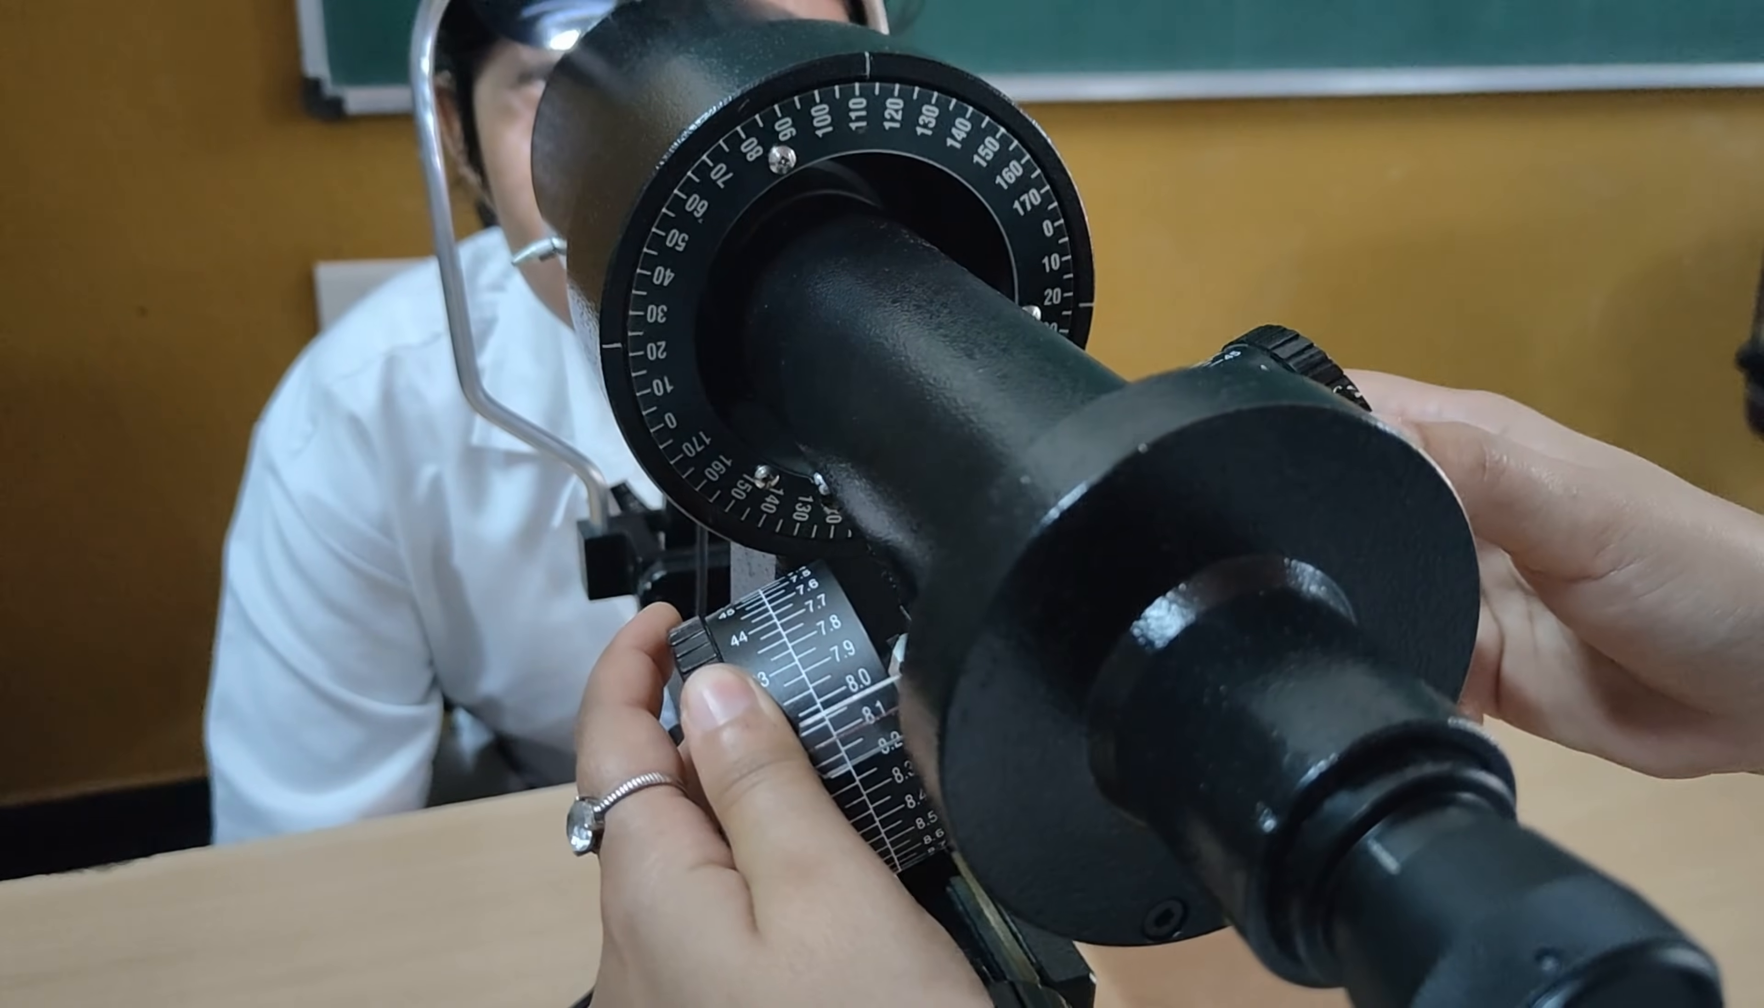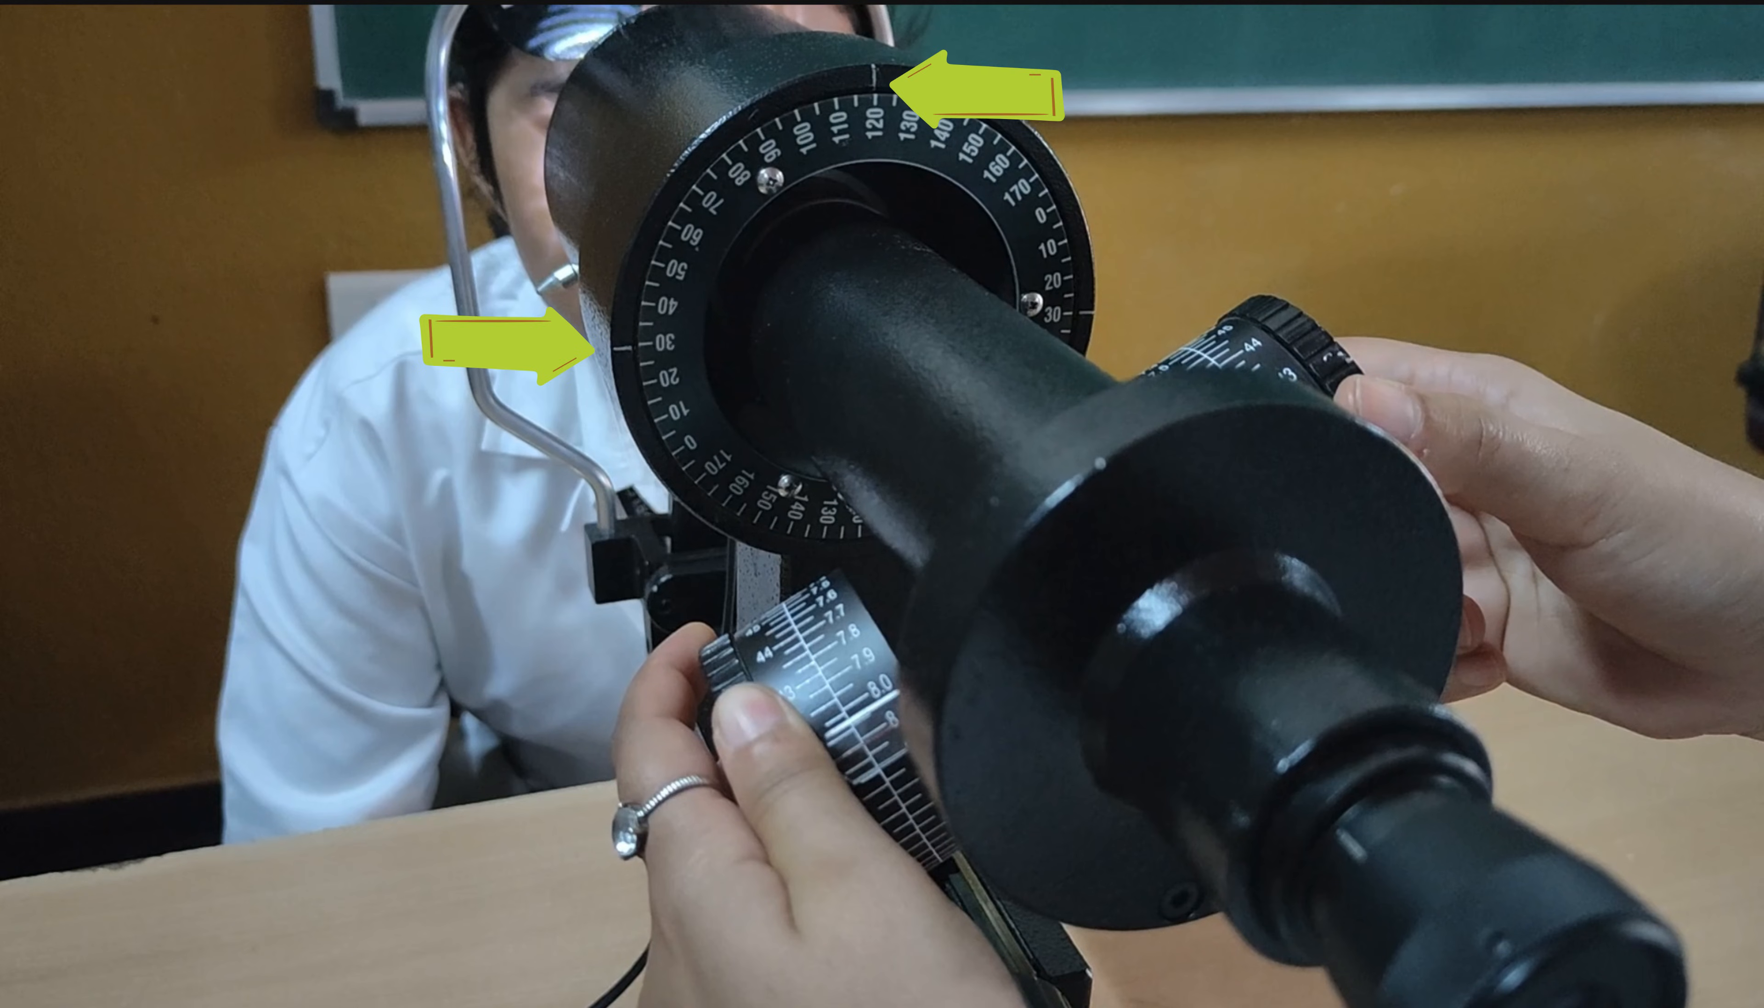In case of oblique astigmatism, mires are not in same plane. In such cases, rotate the instrument until the plus and minus signs are on the same plane. After that, align both plus and minus signs. Record the reading as previously mentioned. But here, axis will be noted from these two points.